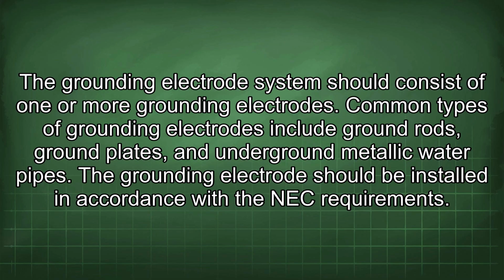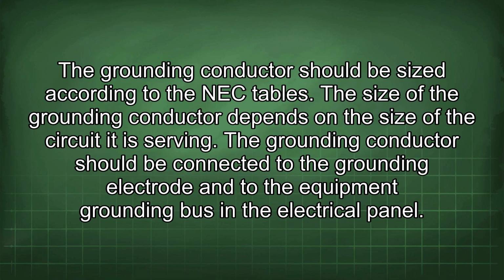Common types of grounding electrodes include ground rods, ground plates, and underground metallic water pipes. The grounding electrode should be installed in accordance with the NEC requirements. The grounding conductor should be sized according to the NEC tables. The size of the grounding conductor depends on the size of the circuit it is serving. The grounding conductor should be connected to the grounding electrode and to the equipment grounding bus in the electrical panel.